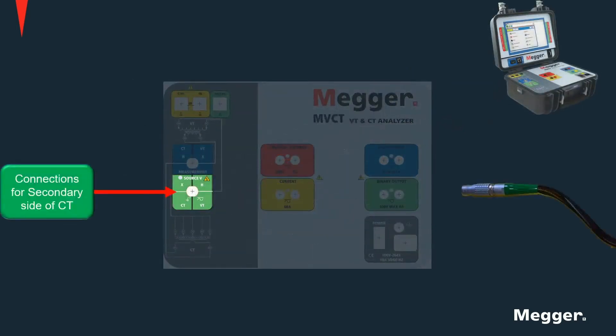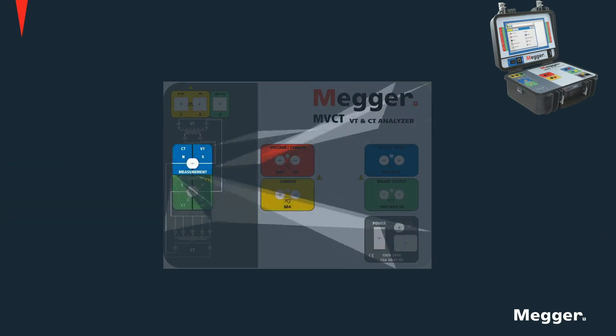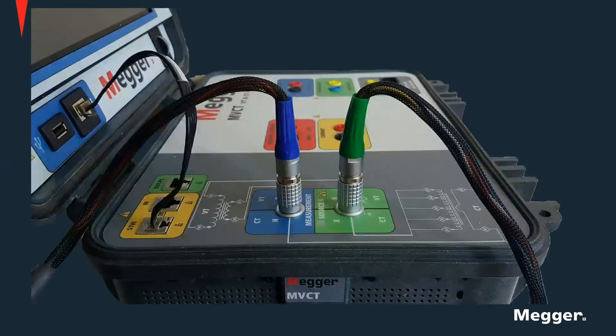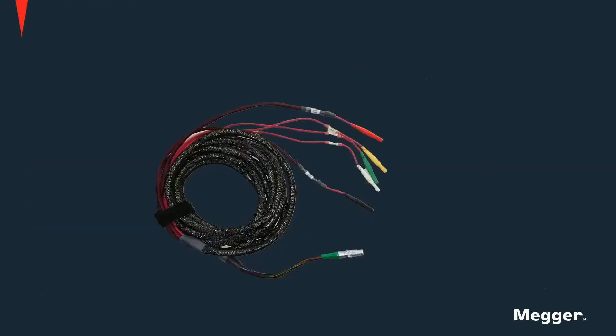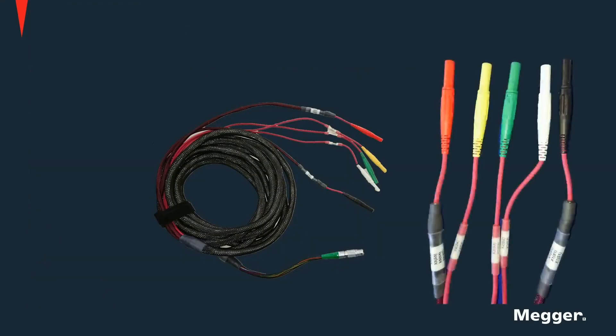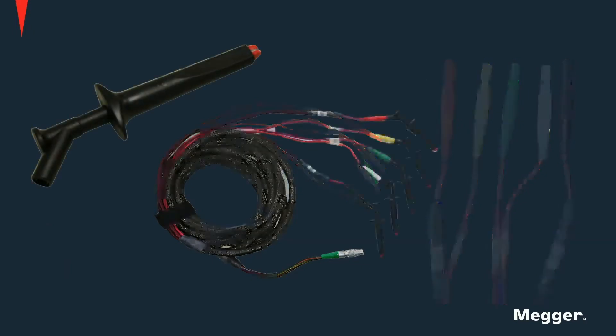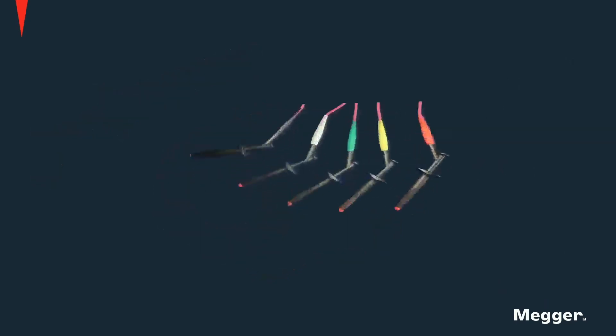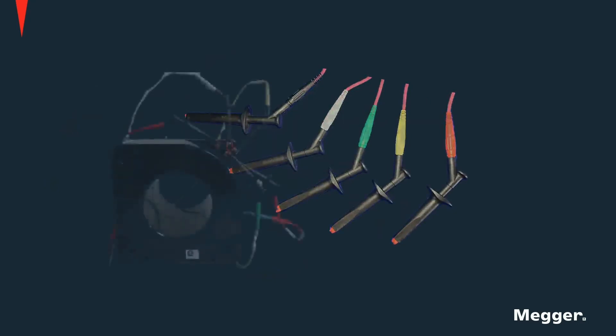Connections are provided for the secondary side of the CT as well as for the primary side of the current transformer. A locking mechanism keeps the primary and secondary cables firmly connected on the instrument, making it impossible for them to get loose or disconnected during testing. Secondary connection cables and alligator clips, which facilitate the job of connecting to a CT under test, are also provided. You can see them here with the alligators connected, and then with the cables connected to a five-tap CT.